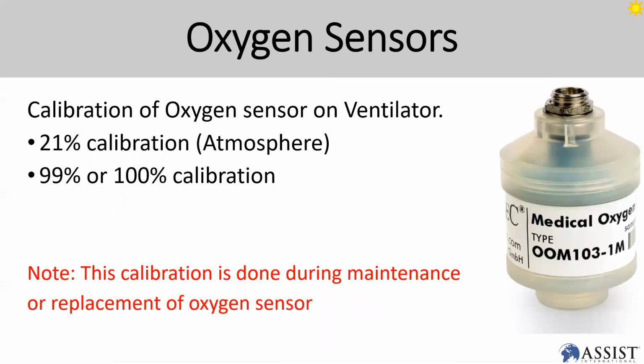Oxygen sensor. Always remember, oxygen sensor plays a very important role in your ICU ventilator. So always make sure it is calibrated and works properly. If you're still not happy with the results, try to verify it with another oxygen analyzer device or with your ventilator analyzer that has an oxygen sensor together. So you can verify the reading, but try to calibrate first.